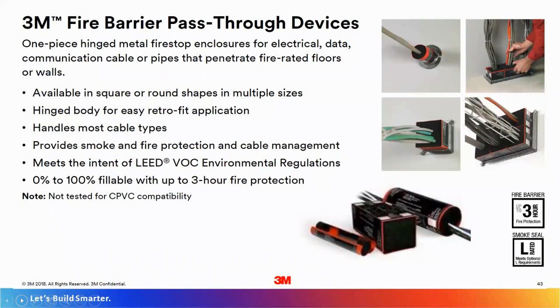The next item here is our pass-through device. This is a one-piece hinged metal fire stop enclosure. Inside the steel sleeve is an intumescent pad. So that intumescent pad, when heated, obviously would expand and choke off the fire and the passage of smoke through the assembly. They're available in square and round configurations in multiple sizes. And the square units can be ganged together to address larger penetrating situations where you have multiple different cables.